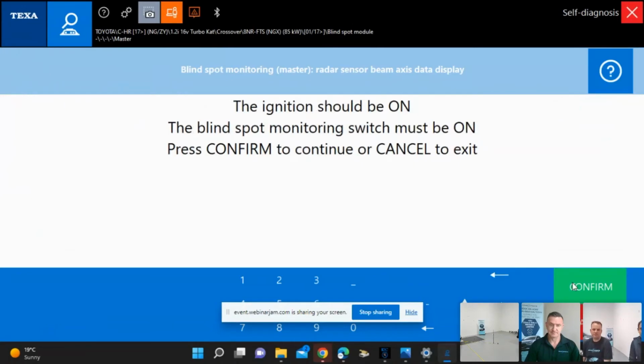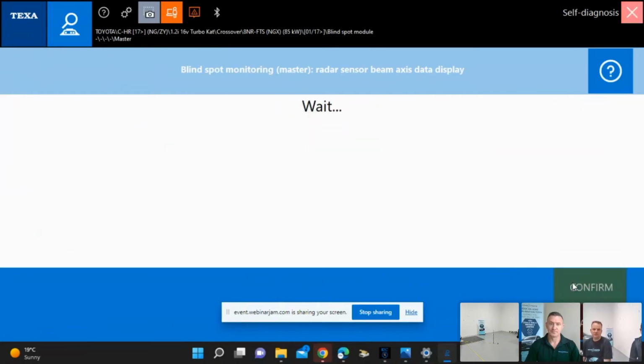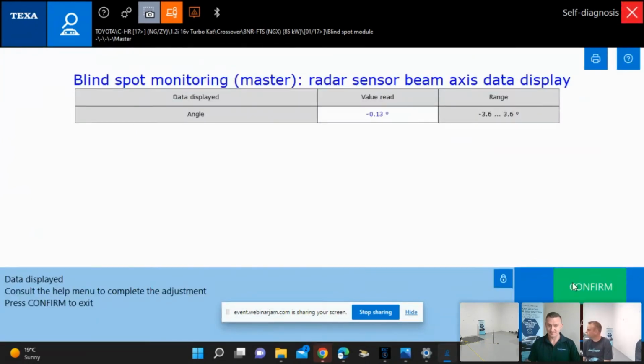What we have now is that cone in a position which is OEM compliant. We see that angle there: minus 0.13 degrees. On the right side, we see the angle needs to be between minus 3.6 and plus 3.6 for a successful calibration. So if we go back and perform the calibration, we'll get that result on screen.